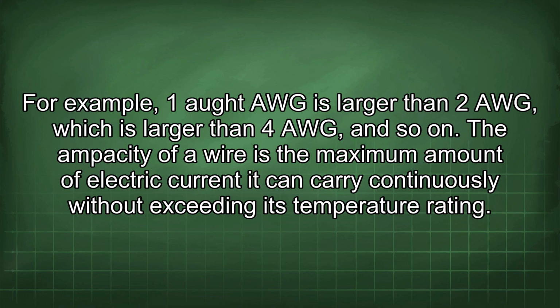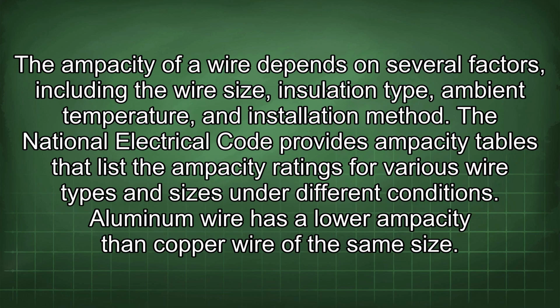The ampacity of a wire is the maximum amount of electric current it can carry continuously without exceeding its temperature rating. The ampacity of a wire depends on several factors, including the wire size, insulation type, ambient temperature, and installation method. The National Electrical Code provides ampacity tables that list the ampacity ratings for various wire types and sizes under different conditions. Aluminum wire has a lower ampacity than copper wire of the same size.